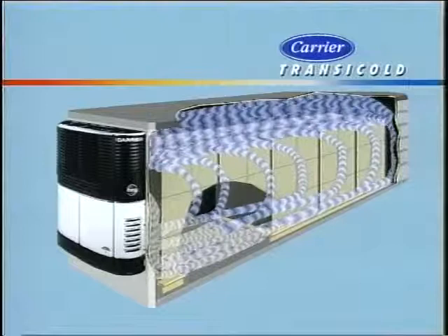If an abnormal condition is sensed, an alarm is automatically registered in the message center. The unit may or may not shut down depending on what the alarm is. Less critical alarms will not let the unit shut down, and the message center will show "Check at next service interval" instead of status OK. Shutdown alarms, such as high discharge pressure, will cause the unit to shut down. Should this occur, the message center will show "Unit shutdown, see alarm list."